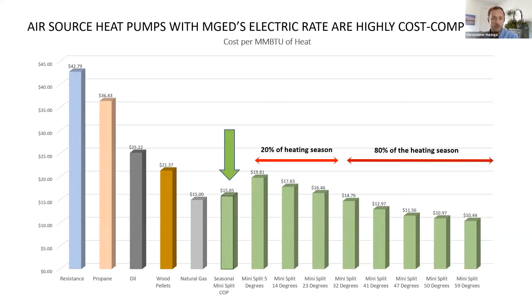Heat pumps are 2 to 4 times as efficient as a gas furnace, even in the coldest climates. This technology has come a long way from traditional electric heating and offers efficiency that fossil fuels just can't match. Air source heat pumps deliver heat at progressively lower costs, the warmer the outdoor temperature. As you can see in the chart, we spend about 80% of our heating season between 32 degrees and above, and only about 20% below freezing. The overall average of the season is represented by the green bar with the arrow, and the bars following it to the right show the cost depending on the outdoor temperature.